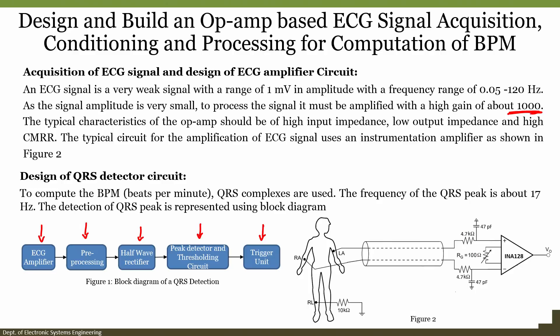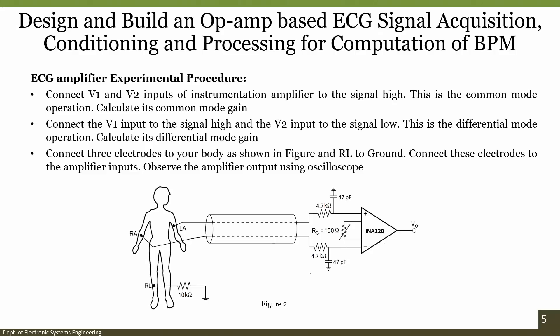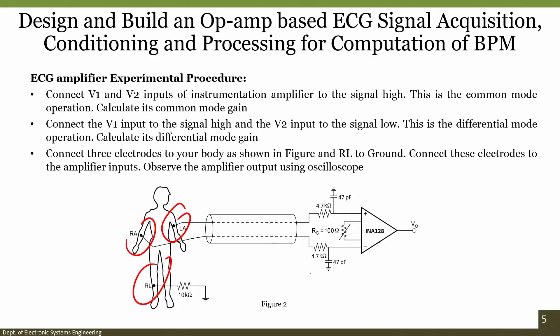Now let us see how to develop the ECG amplifier for QRS signals as well as BPM. First, connect V1 and V2 — the inputs to the instrumentation amplifier — to the signal high. This is the common mode operation and we calculate the common mode gain. Second, connect V1 to signal high and V2 to signal low; this is differential mode operation and we calculate the differential mode gain. Finally, connect all three electrodes — RA, LA and RL — to the body, with RL connected to ground through a 10 kilohm resistor, then connect the electrodes to the amplifier inputs and observe the output on the oscilloscope.